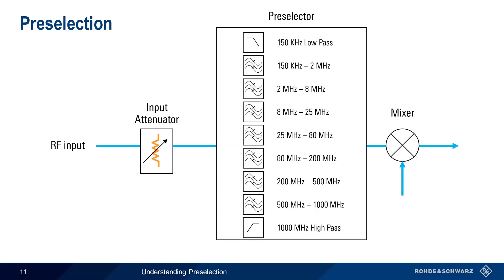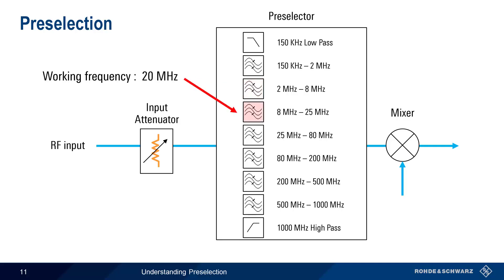Let's look at how a preselector works. Without a preselector, input power at all frequencies is passed to the mixer, regardless of working frequency. When we place a preselector in front of the mixer, our preselector — implemented as a bank of filters — has each filter passing only a certain range of frequencies. Our instrument automatically chooses which filter to use based on our current working or operating frequency. For example, if we're currently at 3 MHz, this filter is used; if we're at 20 MHz, a different filter is used. And if our instrument is scanning over a range of frequencies, the preselector automatically switches between filters at the appropriate times during the scan.